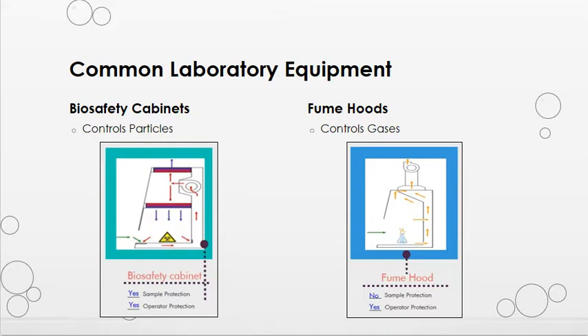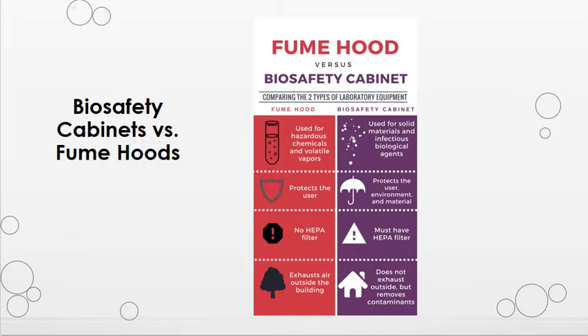Some labs will have fume hoods, but biosafety cabinets will likely be found in the microbiology department. Fume hoods control gases and protect the operator; they should be used for hazardous chemicals and volatile vapors, have no HEPA filter, and the exhaust goes to the outside of the building. Biosafety cabinets, on the other hand, control particles and protect the operator, the environment, and the sample — as long as it's a class 2 or above. They are used for solid materials, particulates, and infectious biological agents, must have a HEPA filter, and recirculate air after contaminants are removed rather than exhausting outside.